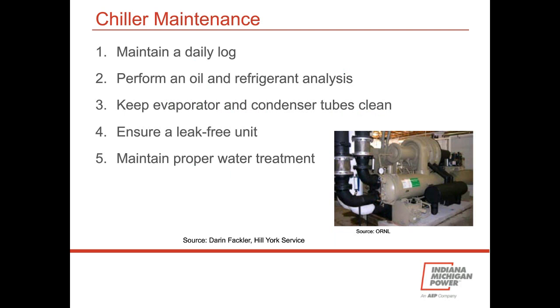So chiller maintenance, here's, again, at least the minimum you should do, these 5 areas. Again, we've been encouraging you to document with a log the performance of your system over time. The oil and refrigerant can be analyzed in a chiller system and give you some good information on how the chiller is performing. We talked about cleaning. We talked about leaks here already as well with our rooftop units. Of course, we have now water involved as well. So let's take a closer look at several of these areas. We'll start with this oil and refrigerant analysis.